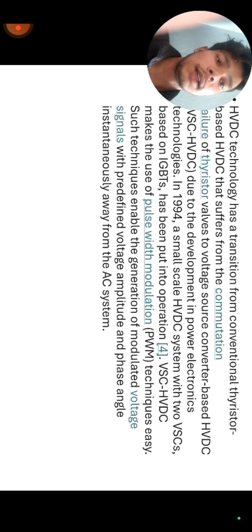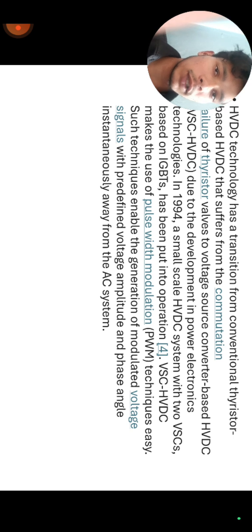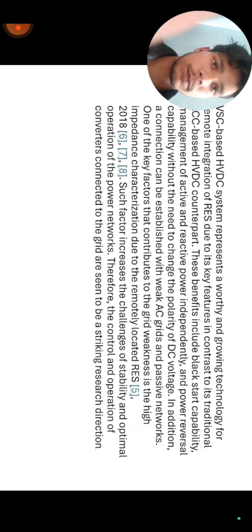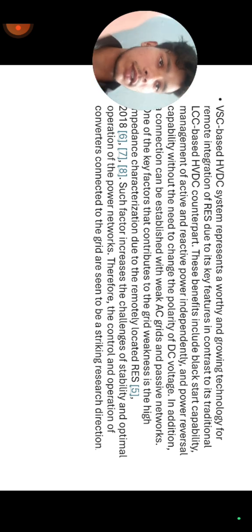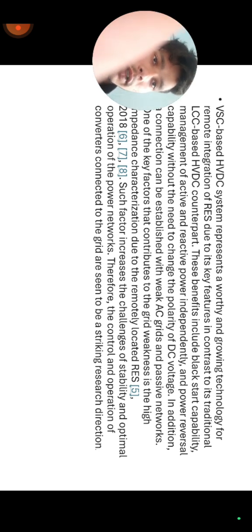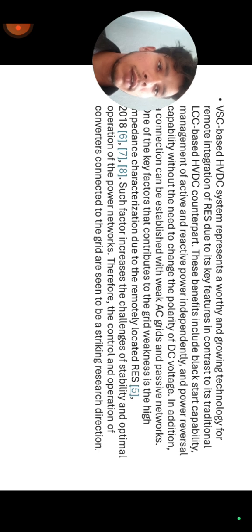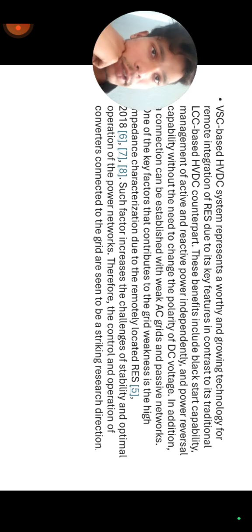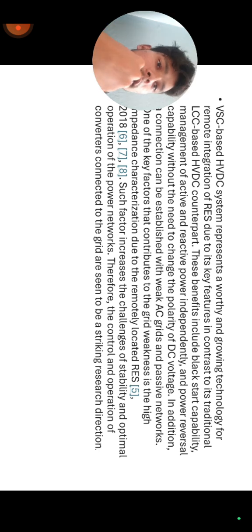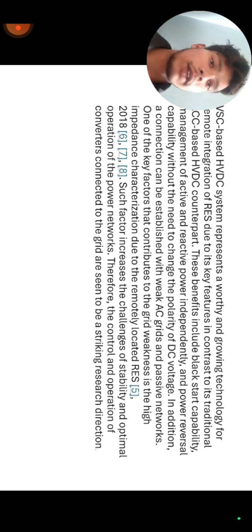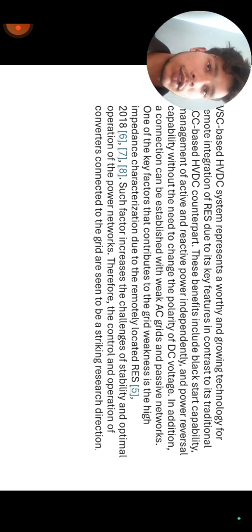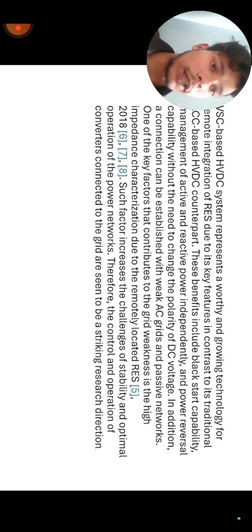Such techniques enable the generation of modulated signals with a predefined voltage amplitude, quite instantaneously, independent of the AC system. VSC-based HVDC is a worthy and growing technology for remote integration of RES due to its key features. In contrast to its traditional LCC-based HVDC counterpart, these benefits include black start capability, management of active and reactive power independently, and power reversal capability without the need to change the polarity of DC voltage. In addition, a connection can be established with weak AC grids and passive networks.